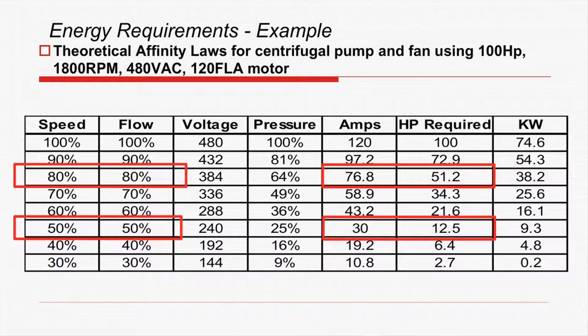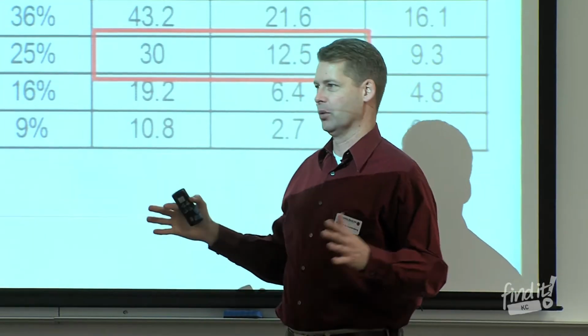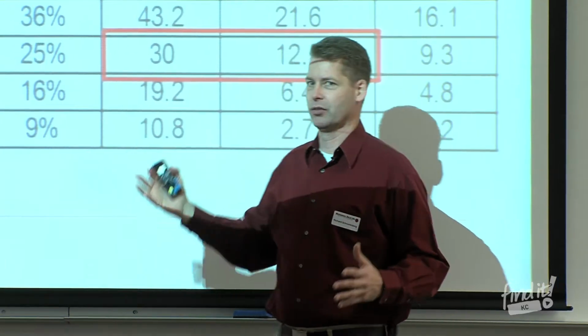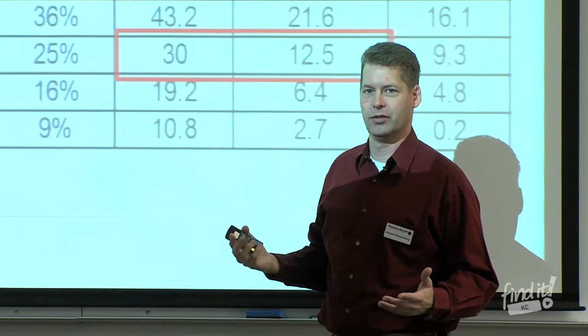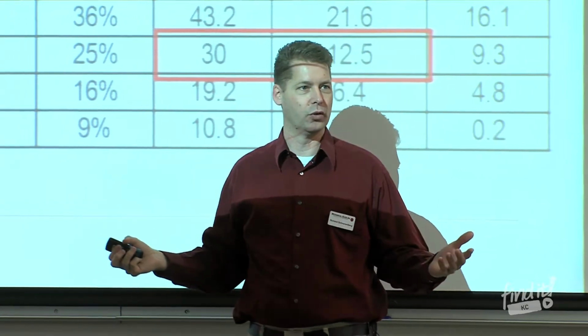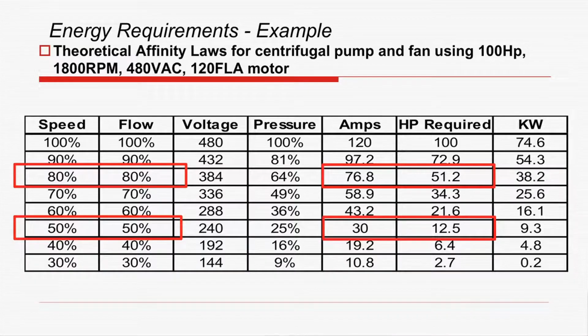So if we've taken a fan and slowed it down to just 80%, that's a common day. You design these systems for your 105-degree days here in Kansas City, but that only happens 3 or 4 days a year. So if we're normally operating at, say, 80% flow and speed, that's not 80% of the energy you're consuming, it's only 50% of the energy you're using.